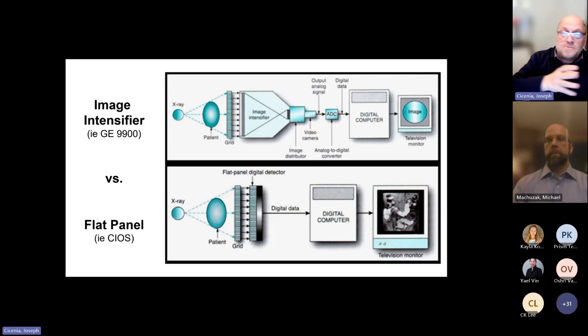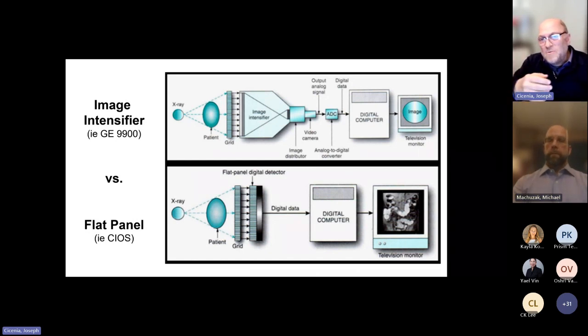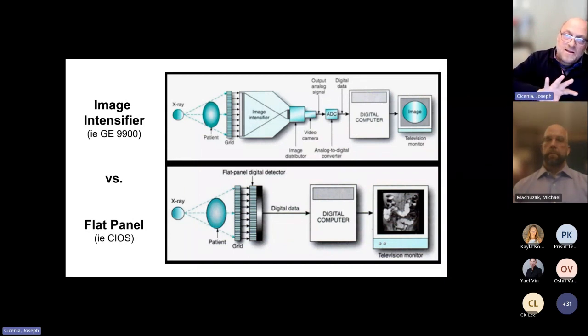So there you do your limited angle sweep, you do your x-ray, it hits a detector, which then has to go through this image intensifier, which hits a video camera, which has an analog output. It goes into this thing called an ADC, which converts the analog signal into a digital signal, goes into a computer, an algorithm is applied, and an image is created.